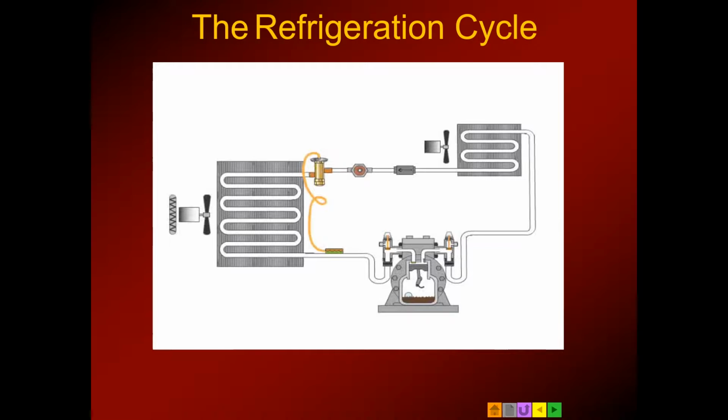The purpose of the expansion valve is to lower the refrigerant pressure by creating a pressure drop. As the liquid refrigerant passes through the expansion valve, the high temperature liquid changes to a low temperature vapor due to the drop in pressure. Around 25% of the liquid boils off, dropping the temperature of the remaining liquid from 115 degrees to 40 degrees. That temperature remains the same through the evaporator as it absorbs latent heat from the conditioned space.